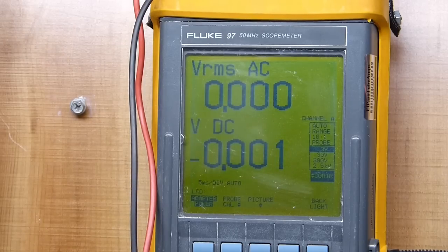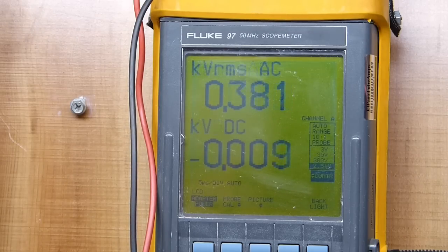Each side of the high voltage transformer going into the rectifier is 380 volts—that's 380 volts each side of the center tap. So if you double that, it would be 760 volts, center tapped. That's what that is, okay.